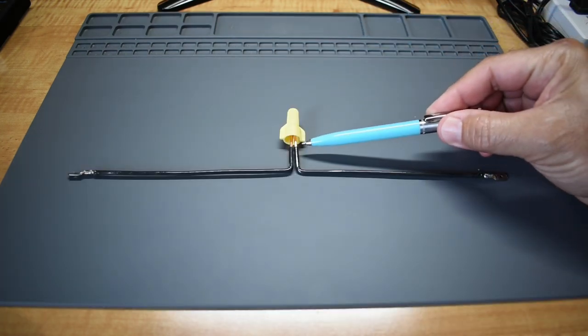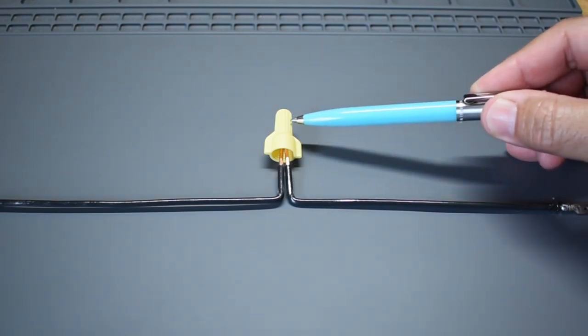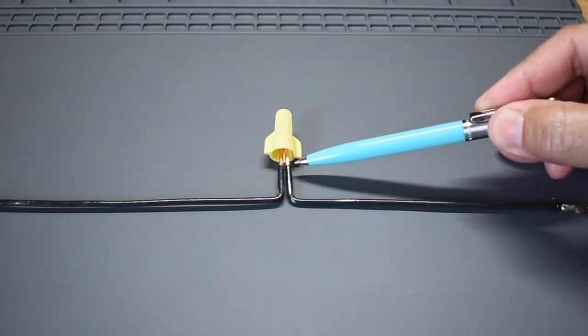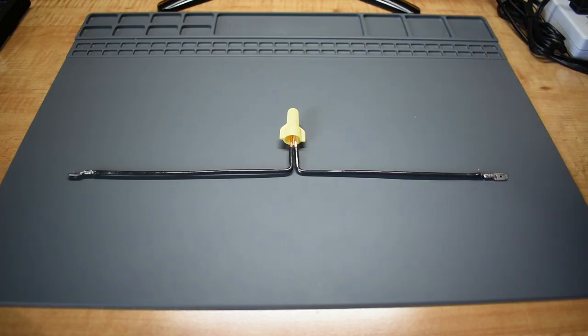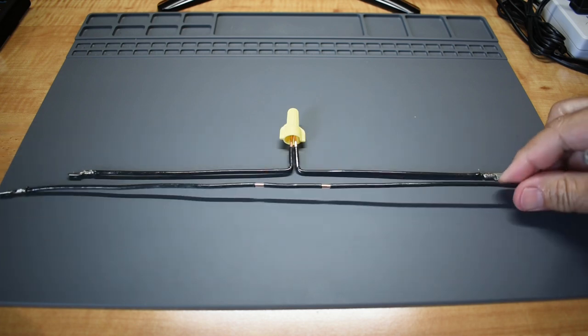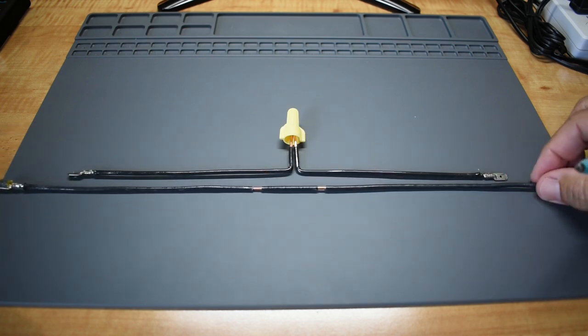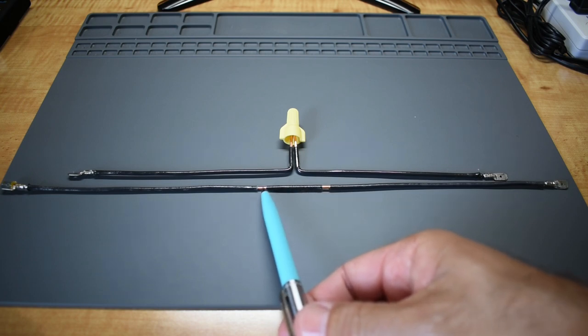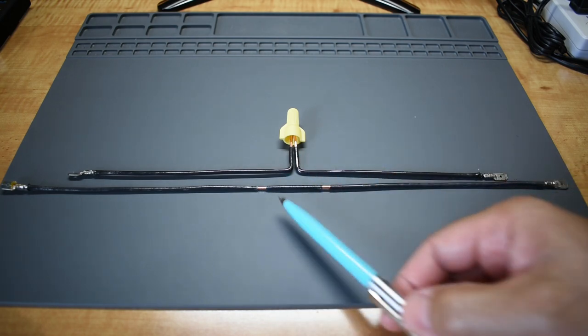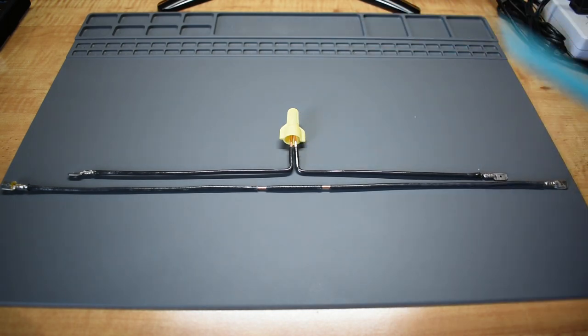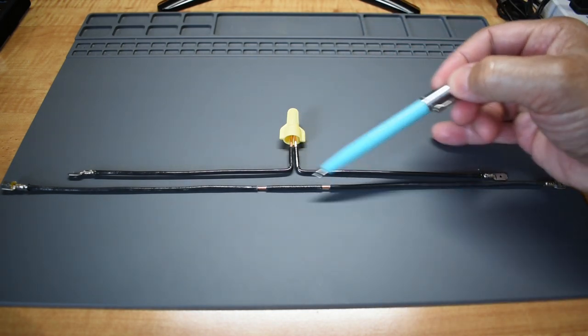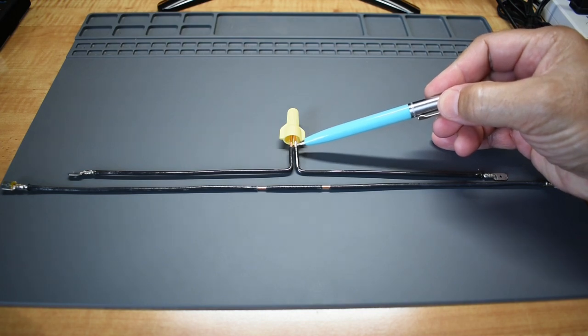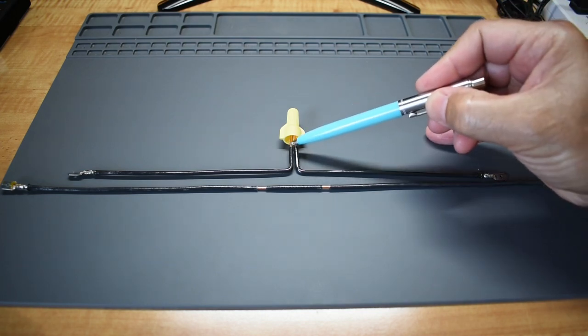Over here is the wire nut, all ready to go. You can see the conductor was stripped between here and the end where they're twisted together. Now this area is about 20 millimeters or 3 quarters of an inch. And the reason for that is because if you look at the wire that is uncut from the center here, if you cut it to there, would be the distance with the insulation removed going in. I'm going to measure the voltage here on the wire. And for this one, I'll measure on this side and on the opposite side.